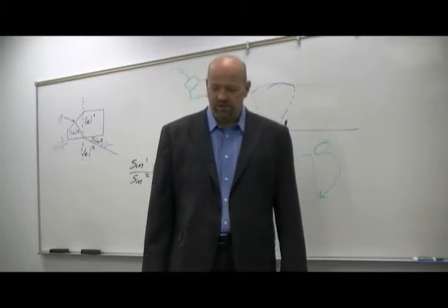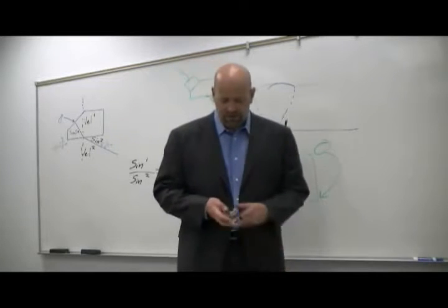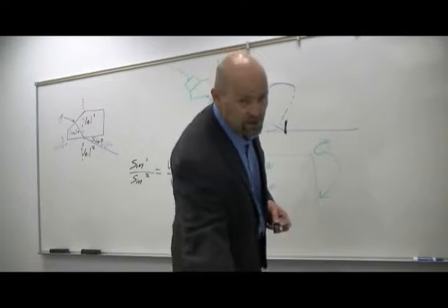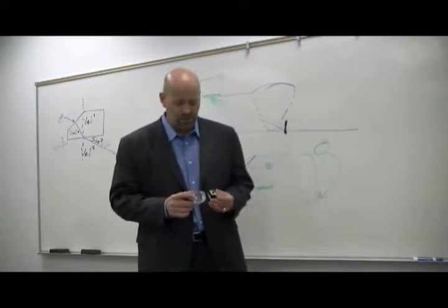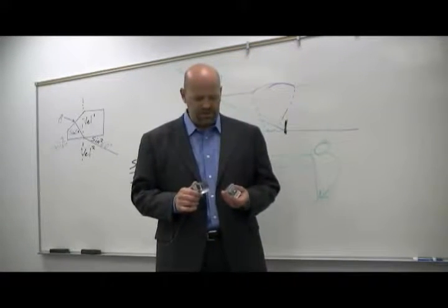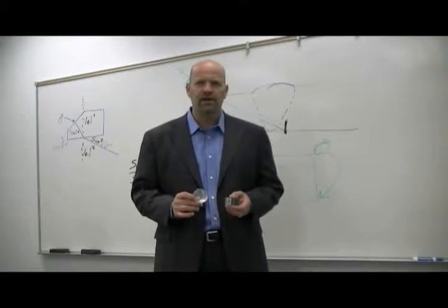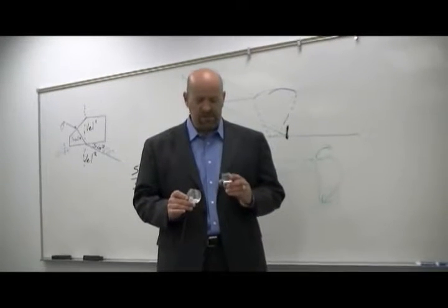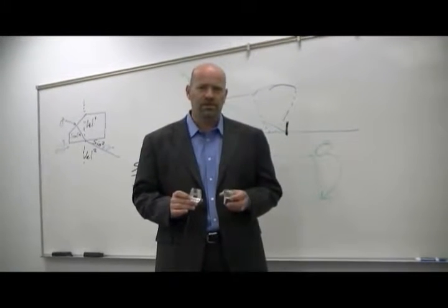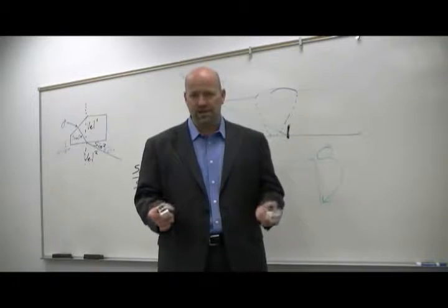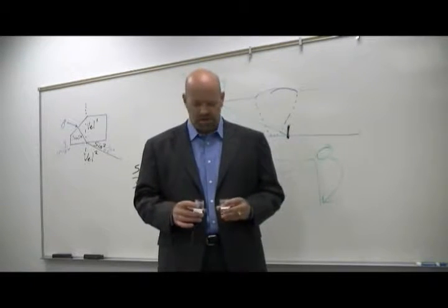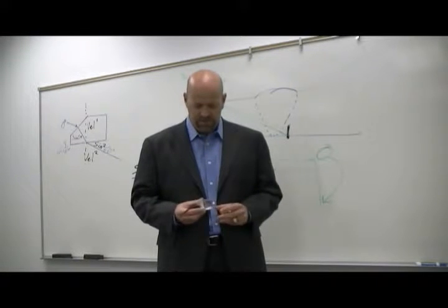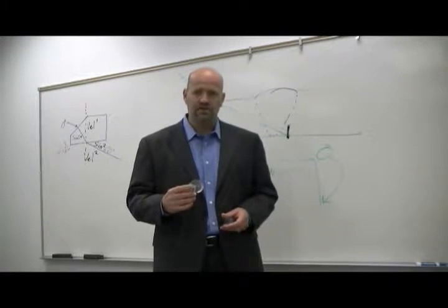What we did is we took the most popular selling conventional probe that we make, and then we built an array to mimic it. Now, one of the things that people have a hard time understanding is an array of a given size will have the exact same acoustical properties as a conventional probe of the same size. So what you end up with is pretty much apples to apples. And as you can see, we even use the standard conventional wedge for it.